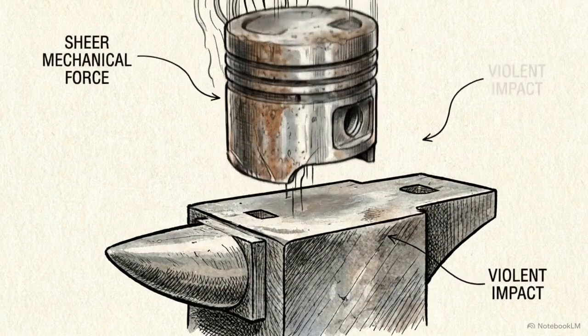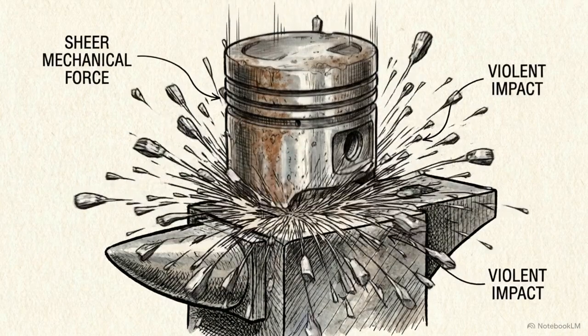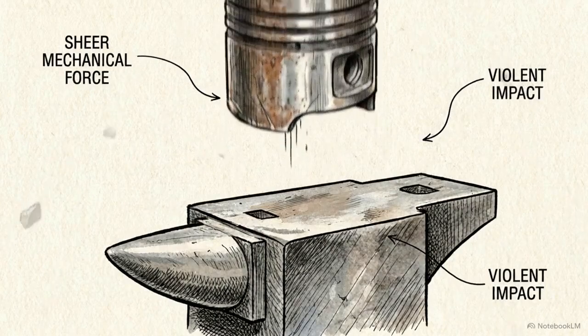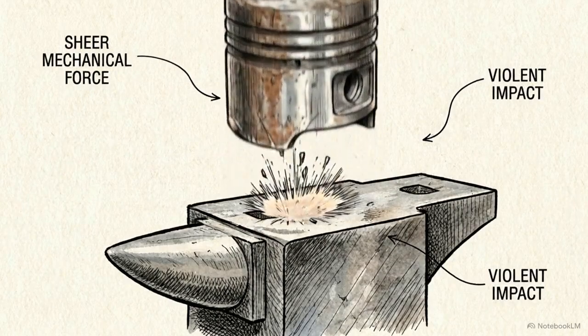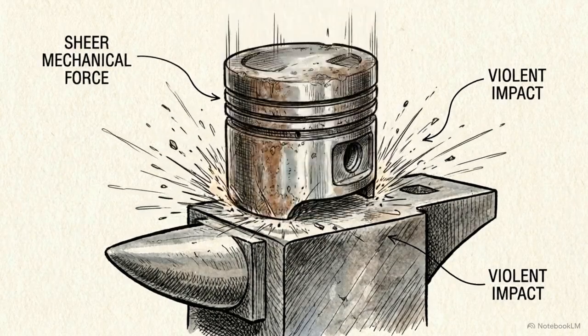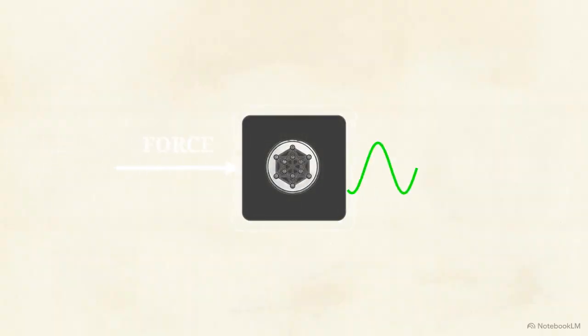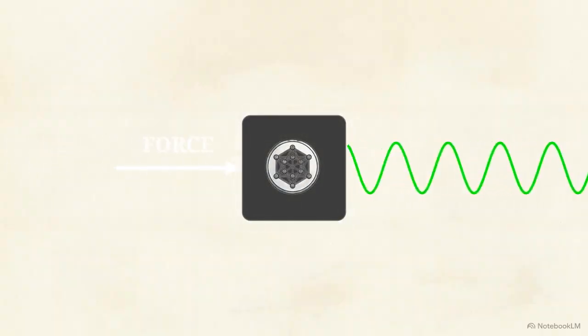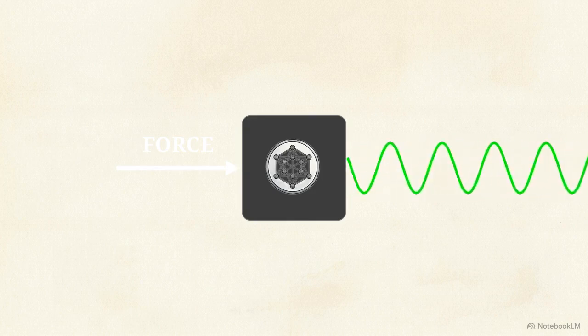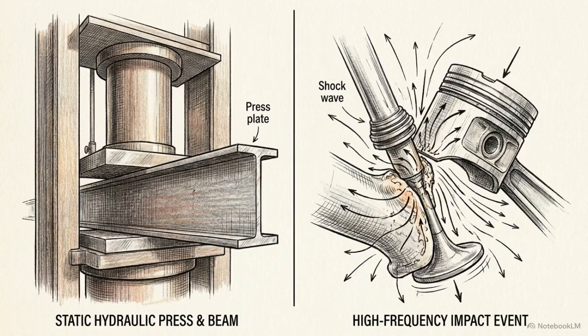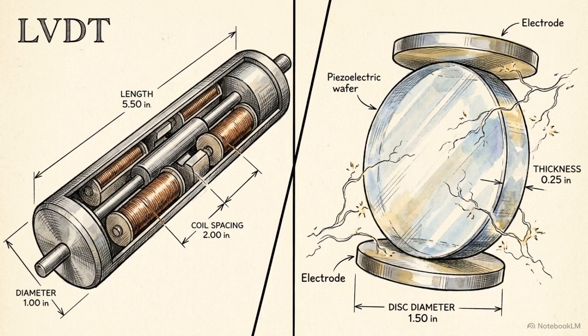Capturing raw physical reality, like the force of a high-velocity piston, and converting it into a calibrated electrical signal is the central challenge of instrumentation. Transduction is the active exploitation of fundamental physics to capture movement, force, and pressure. But measuring a slow, static change requires a physical architecture that is entirely different from one designed to capture high-frequency impacts. For precise geometric measurement, engineers rely on the linear variable differential transformer, or LVDT.